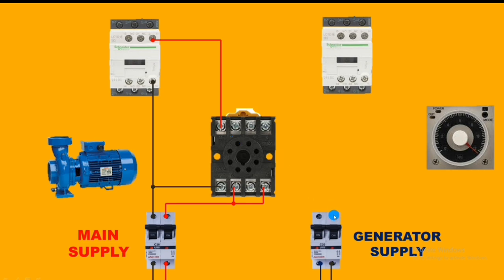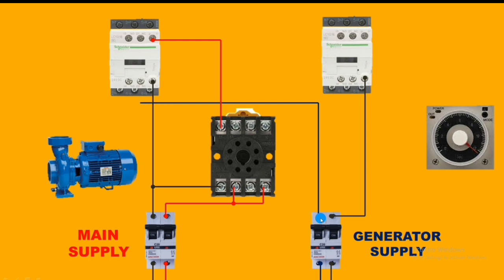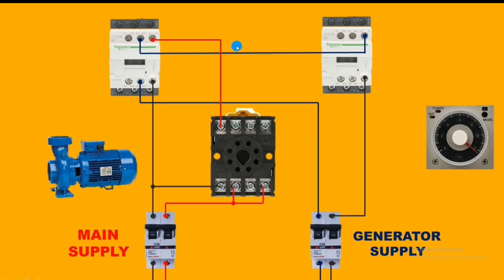Now let's see the connection for the generator power supply. Neutral connects directly to the A2 coil, and the line first connects to the main contactor at the NC point. If the main contactor is in stop condition, this supply will pass. If the main contactor is running, the supply will not pass. If the main power supply is cut, the NC supply connects to the generator contactor A1 coil. So the generator contactor will operate only when the main contactor is in stop condition.